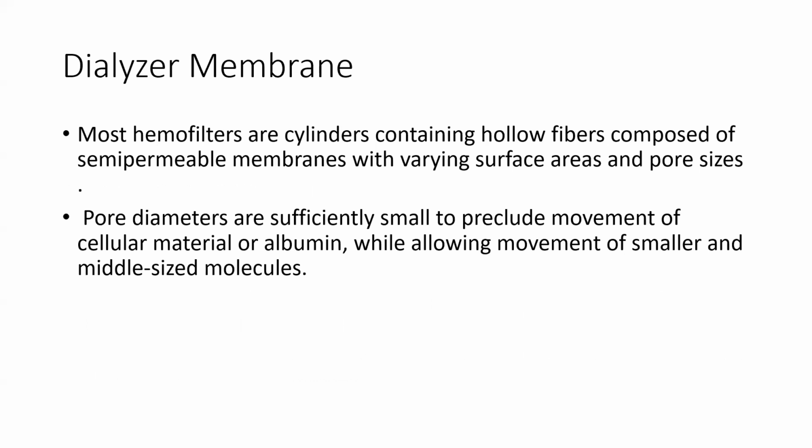Now, the dialysis membrane. Most hemofilters are cylinders containing hollow fibers composed of semi-permeable membrane with varying surface areas and pore sizes. Pore diameters are sufficiently small to preclude movement of cellular material or albumin while allowing movement of smaller and middle-sized molecules.